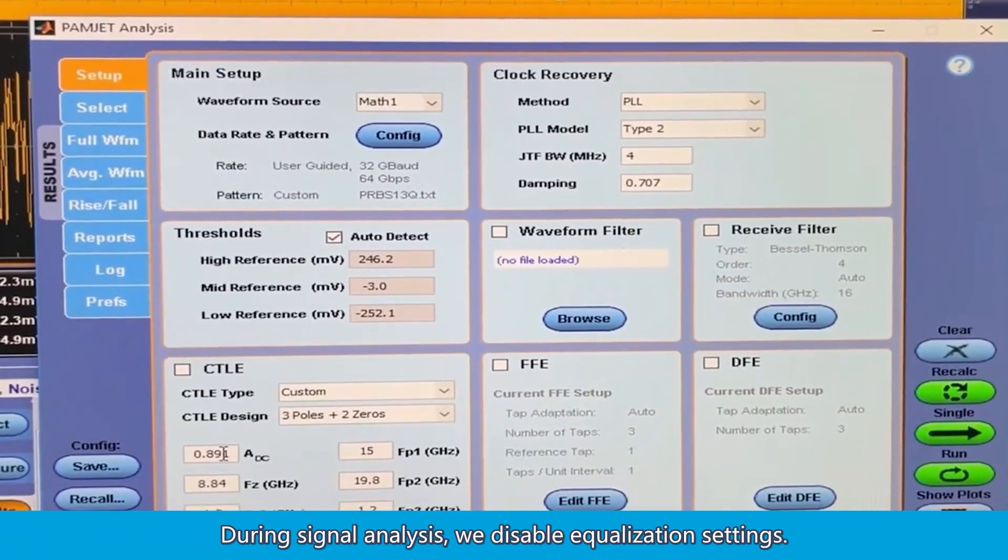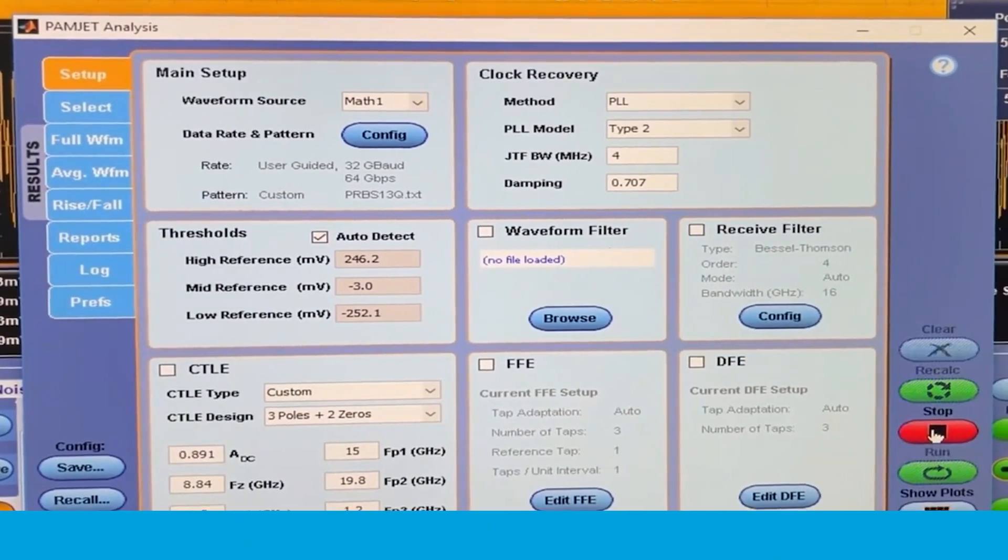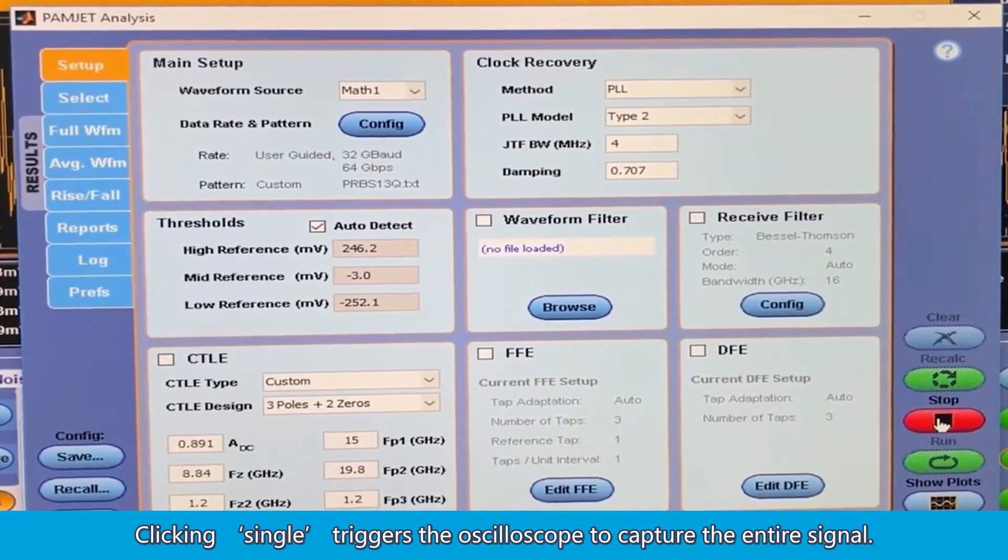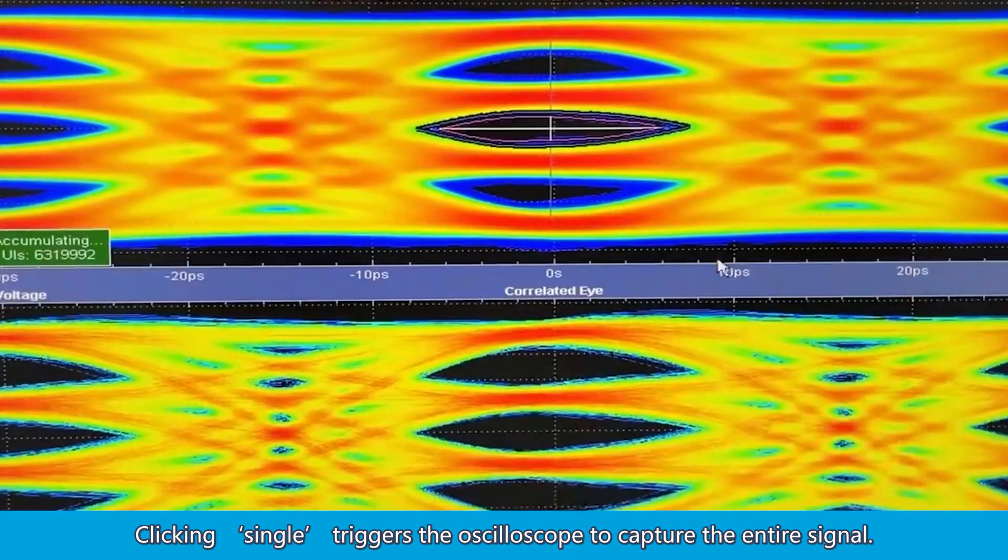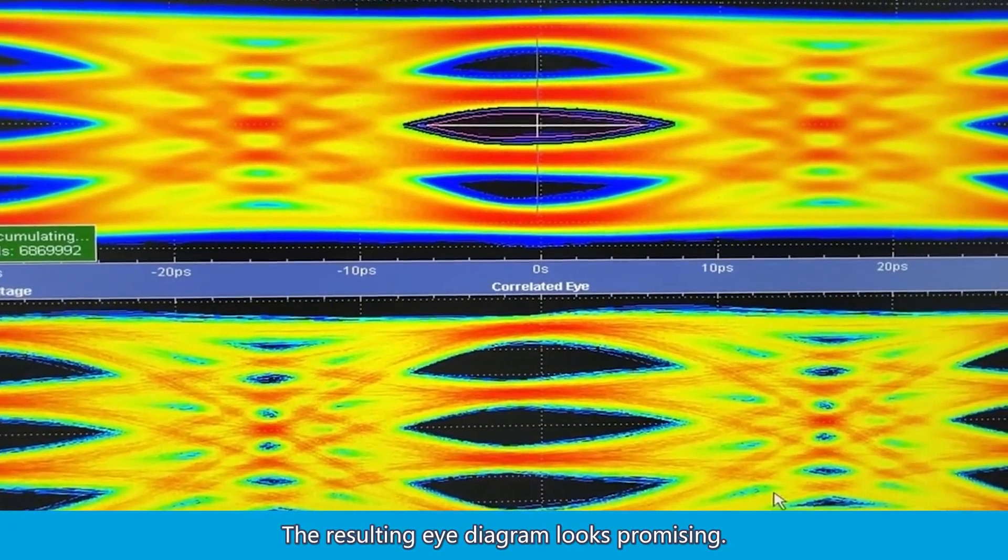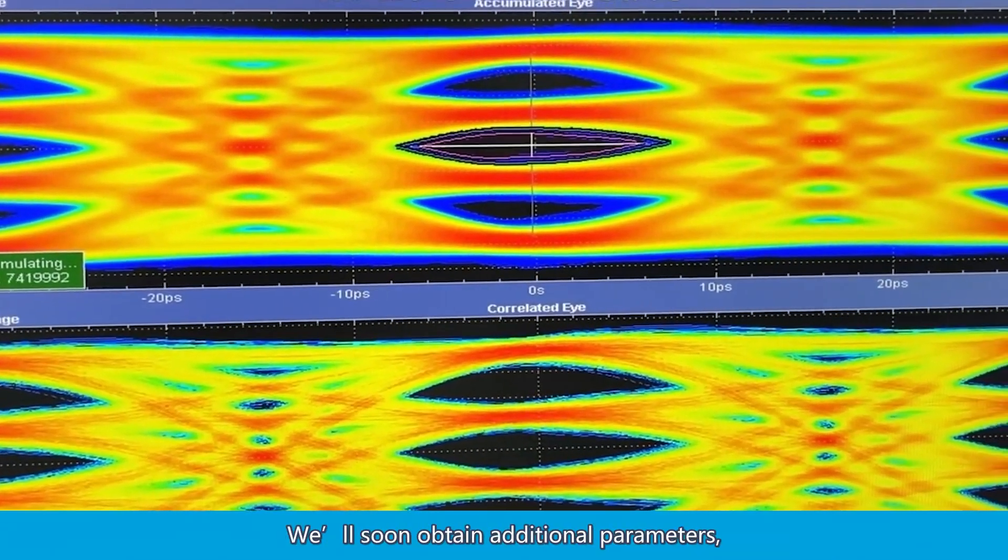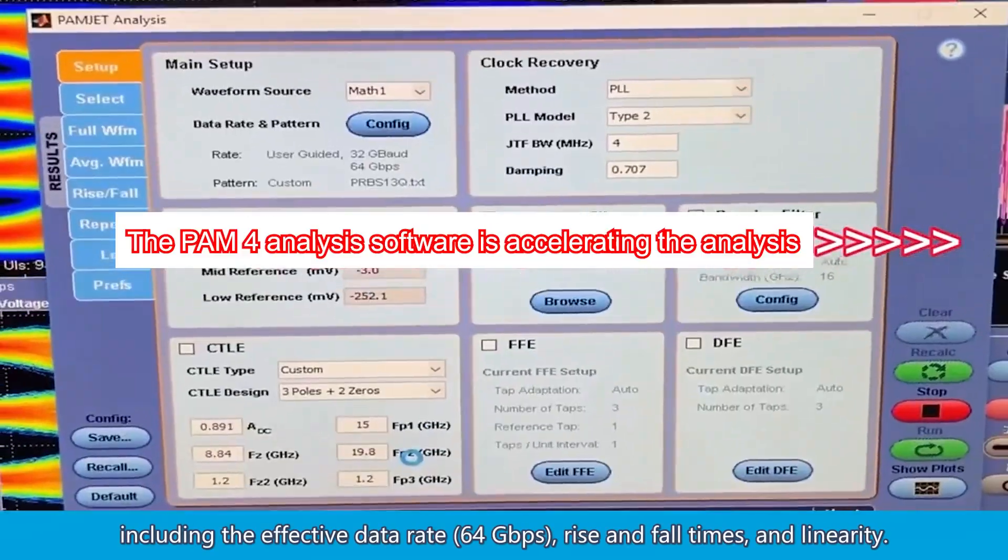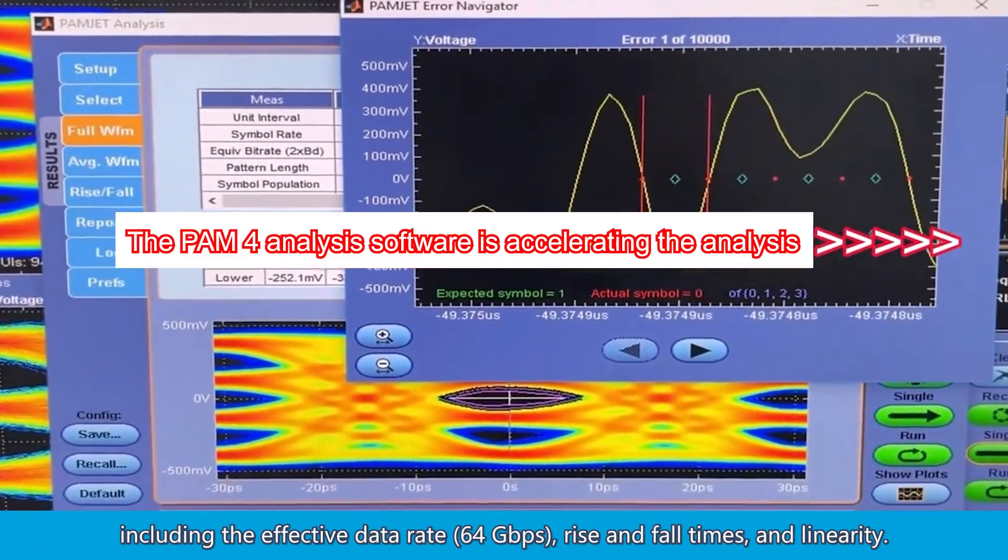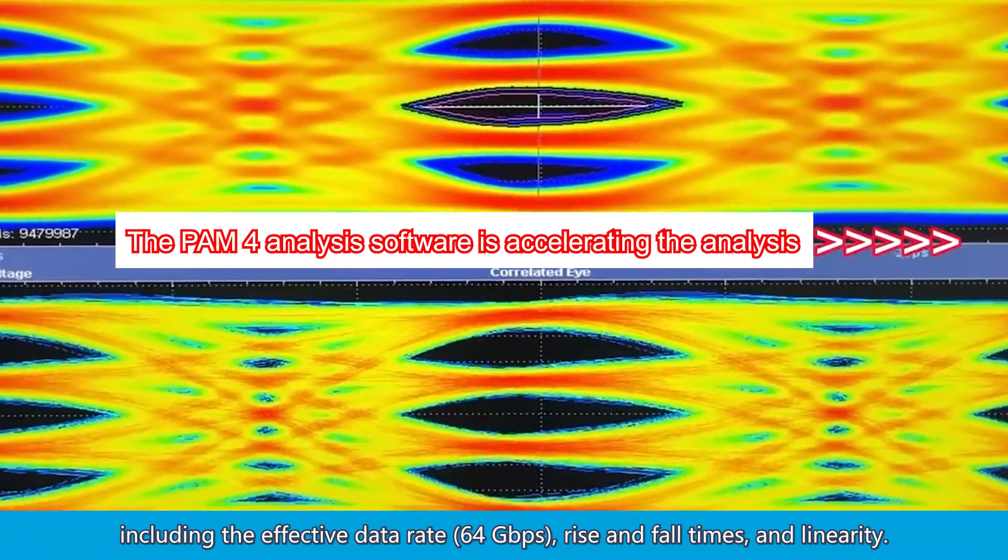During signal analysis, we disable equalization settings. Clicking single triggers the oscilloscope to capture the entire signal. The resulting eye diagram looks promising. We'll soon obtain additional parameters, including the effective data rate, 64 gigabits per second, rise and fall times, and linearity.